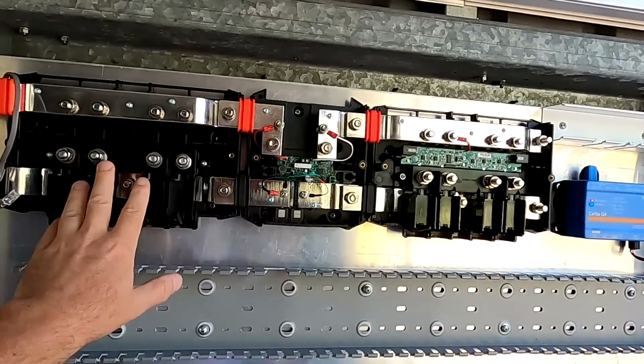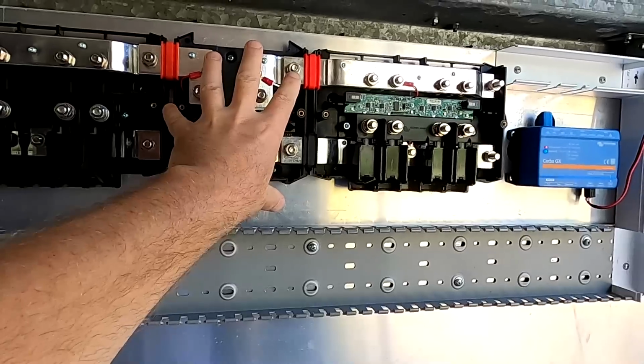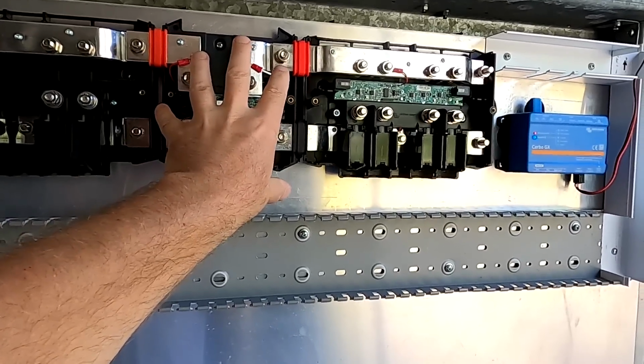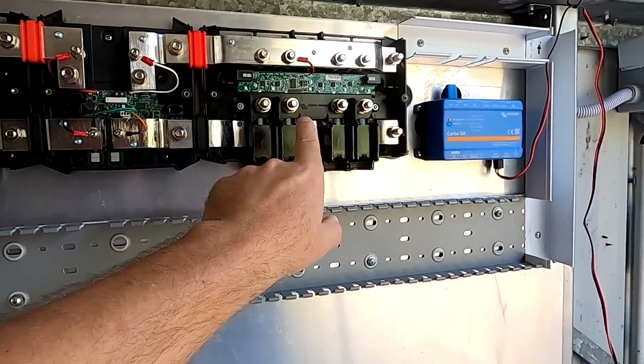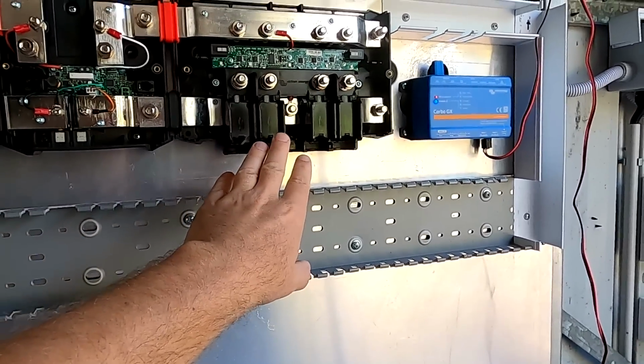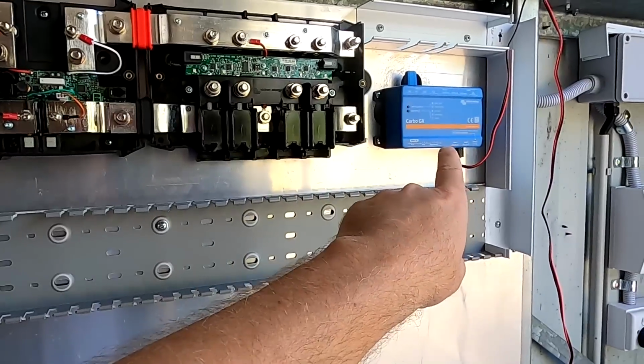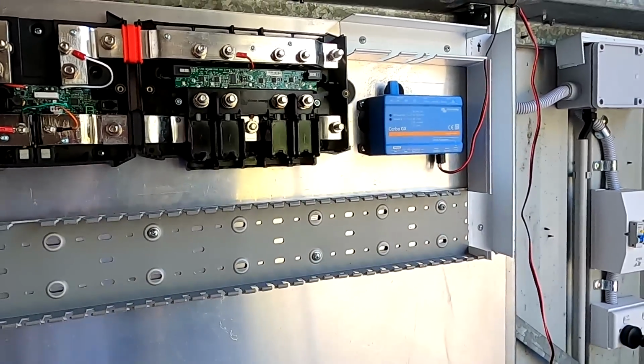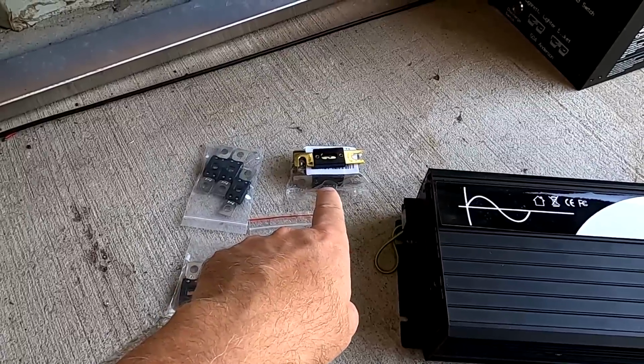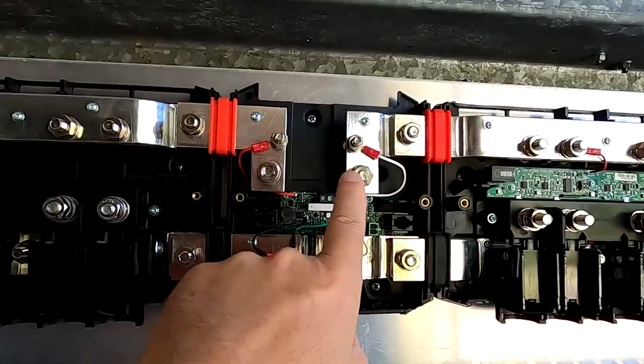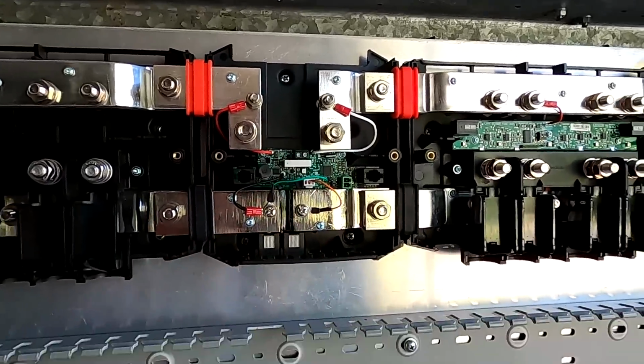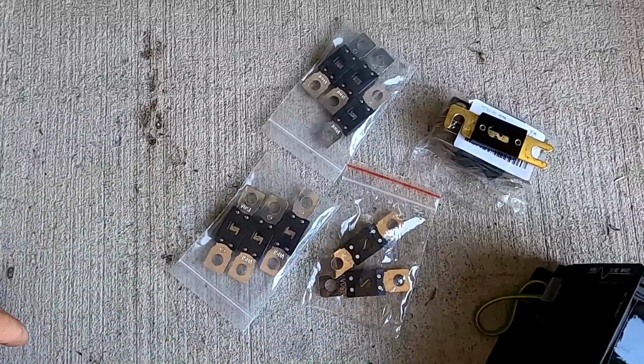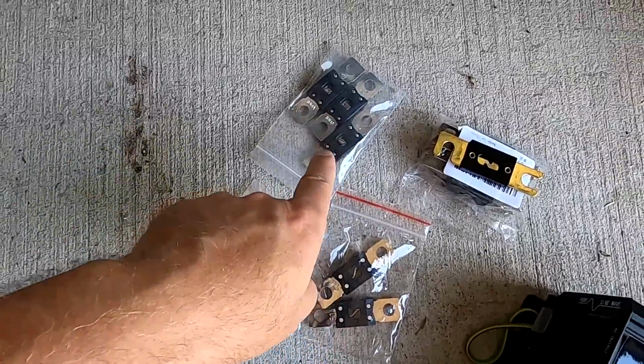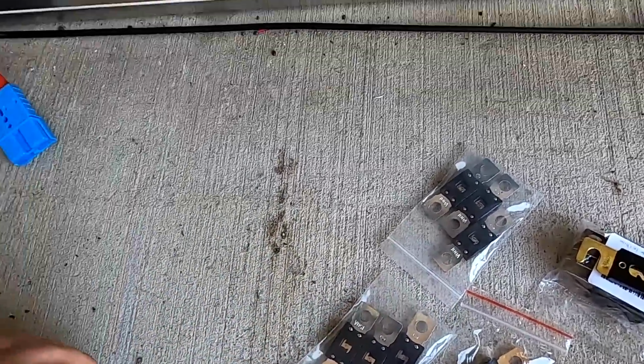So the batteries will go on this side. Then we've got our shunt here, which we may use or may not use, and we've got our Lynx distributor here, where we connect our solar charge controllers and the load, and the Cerbo GX here as our control system. I also have 300 amp ANL fuses, which will be our main fuse in the Lynx shunt, and I also have a variation of mega fuses from 50 to 100 and 150 amps to connect our batteries and loads. That should be totally sufficient.